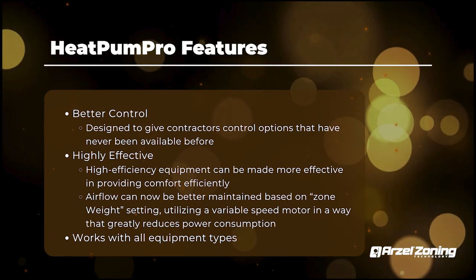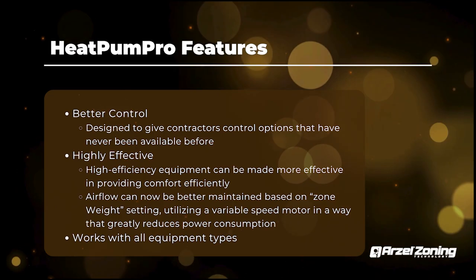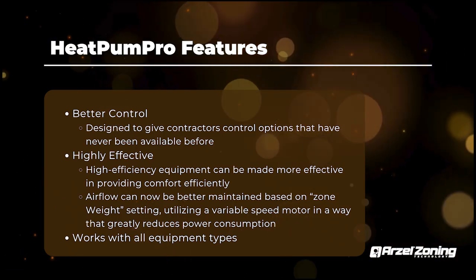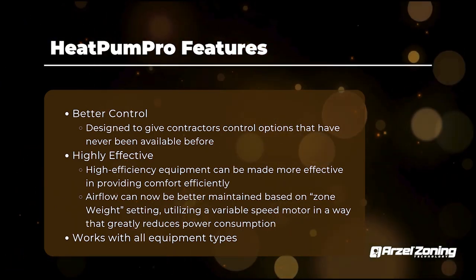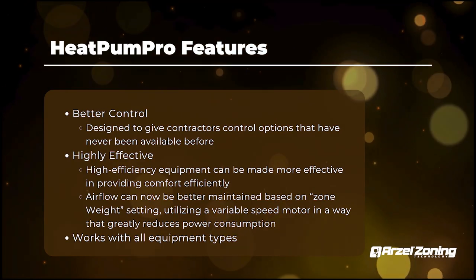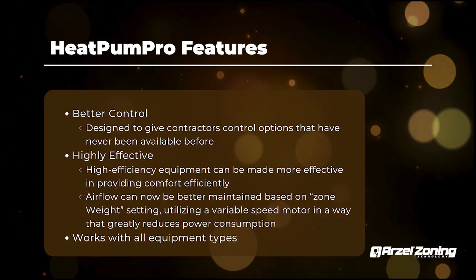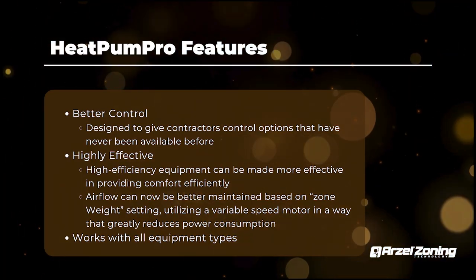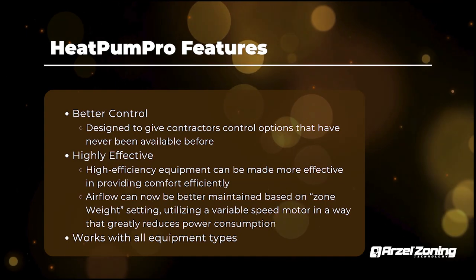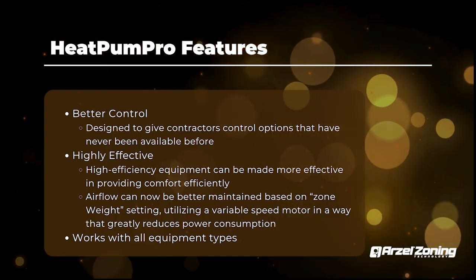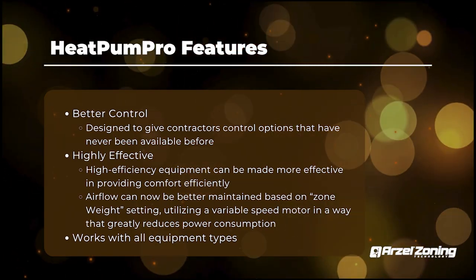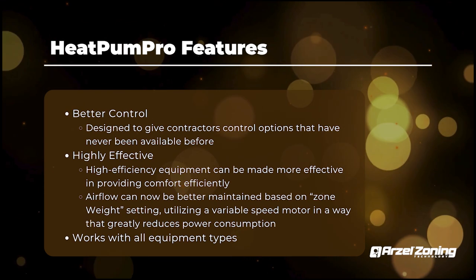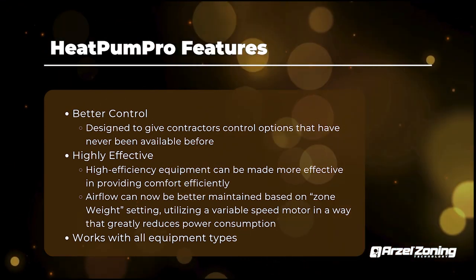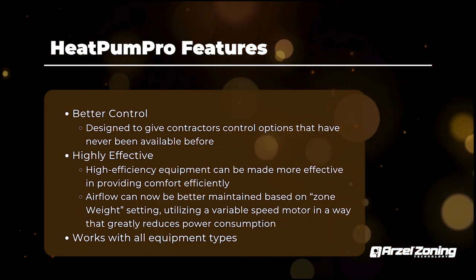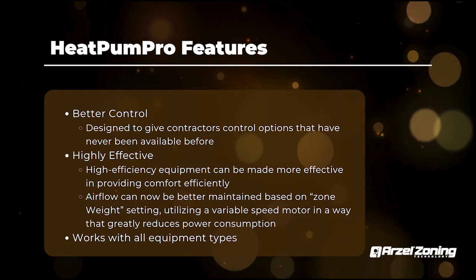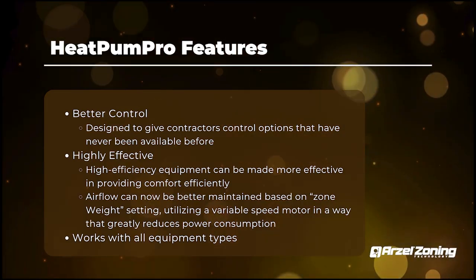The reason that the HeatPumPro was designed originally was just for heat pumps. So it has a lot of features built in for controlling your electric resistance heat. It also has all of your dual fuel settings. And then since it's been adapted in the field, we have done revisions to it. So at this point, the HeatPumPro is really our go-to panel. It'll work for single stage conventional, it'll work for dual fuel, it'll work for two-stage equipment. It really gives you the most bang for your buck on setup and application with the HeatPumPro.